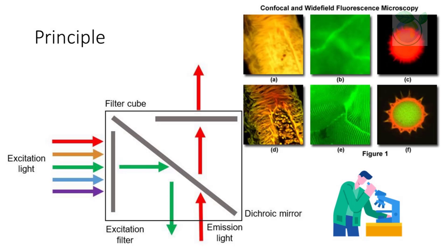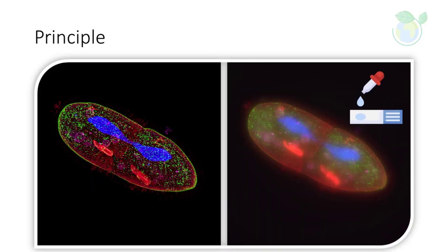In contrast, a confocal microscope uses point illumination and a pinhole in an optically conjugate plane in front of the detector to eliminate out-of-focus signal. The name confocal stems from this configuration. As only light produced by fluorescence very close to the focal plane can be detected, the image's optical resolution, particularly in the sample depth direction, is much better than that of wide-field microscopes.